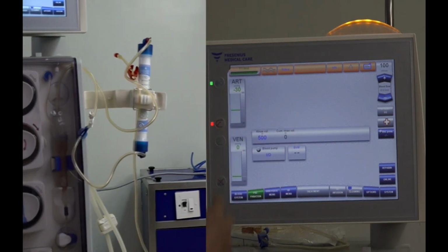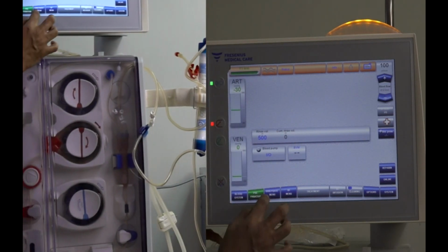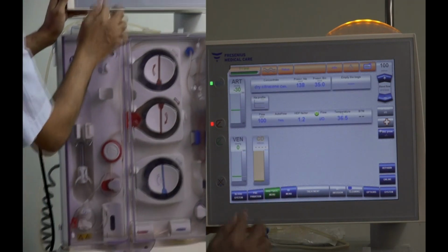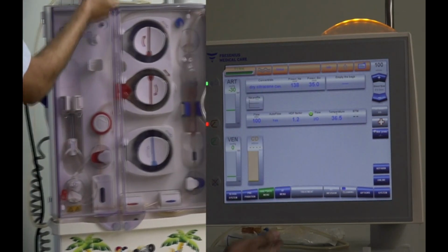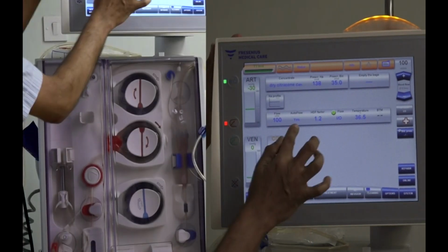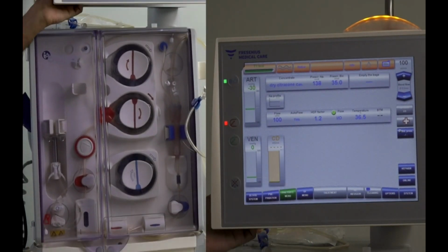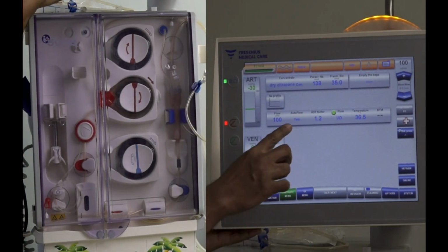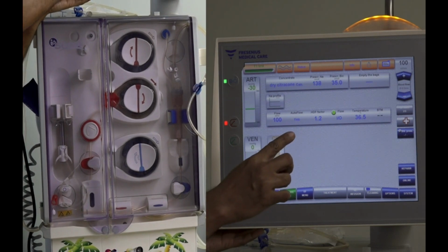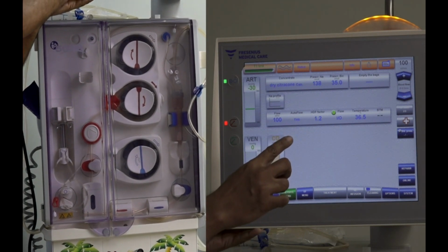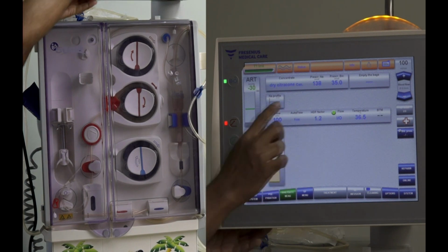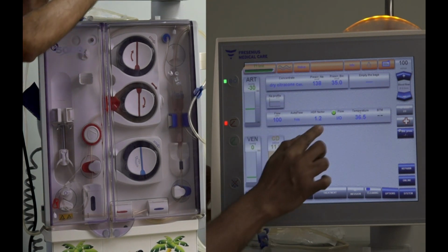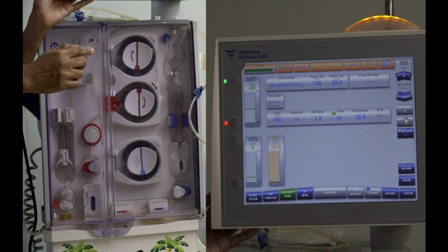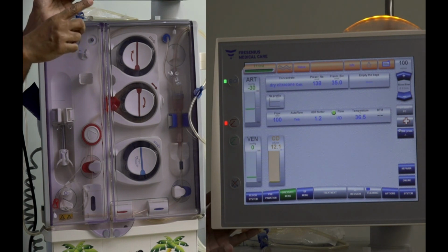The machine self-test is almost completed. Here we can see in the dialysate menu that we have an option of auto flow. If a vascular access is not producing an adequate blood flow, we can set the auto flow on. When we set auto flow, we choose an auto flow factor. The default setting here is 1.2, which means the dialysate flow will be set at 1.2 times the blood flow.